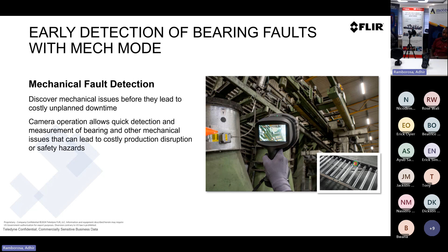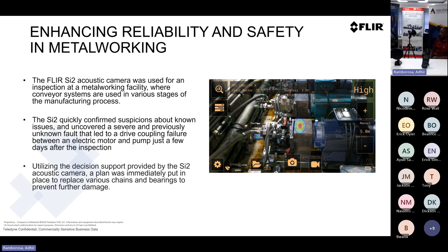If we start to look at some bearing failure and bearing components, when that ultrasonic spike happens there are other technologies that can be used that can be quite tedious. This is one of the easiest devices to detect this. If you look at the mech mode, it gives you crest and kurtosis factors, which become quite important when detecting bearing failure and faults. But I think the point that you can visualize it first becomes rather important.